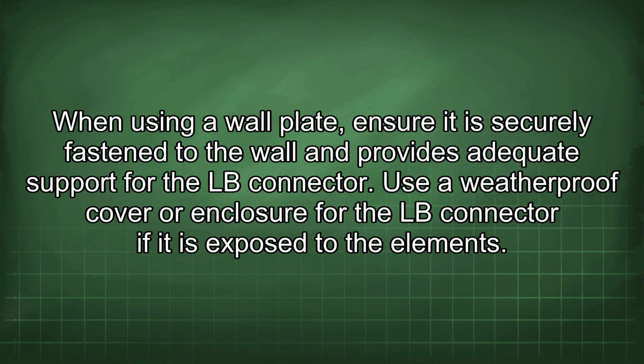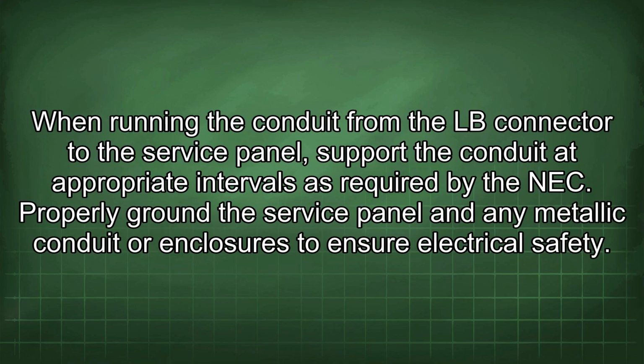When using a wall plate, ensure it is securely fastened to the wall and provides adequate support for the LB connector. Use a weatherproof cover or enclosure for the LB connector if it is exposed to the elements. When running the conduit from the LB connector to the service panel, support the conduit at appropriate intervals as required by the NEC. Properly ground the service panel and any metallic conduit or enclosures to ensure electrical safety.